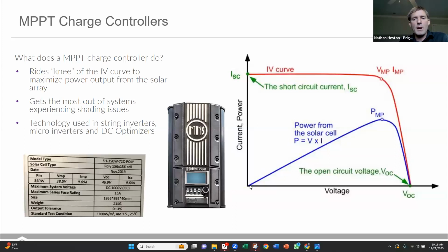And what you can see is power is plotted here as well on this blue line. And if I take the product of current times voltage everywhere on this red curve, I would have the area under my curve, or the size of the rectangle I could draw. And that increases until I get to this part on the knee, which is called the maximum power point. If I decrease my current further and increase my voltage, I get a drop off in power, and that is exemplified here. So eventually, if I decrease my current all the way down to zero, I'm back to zero power again, because even though I have the most voltage my panels put out, open circuit voltage, I have no current being drawn. And so what these MPPTs are doing is constantly stepping forward and backward to stay on that knee.